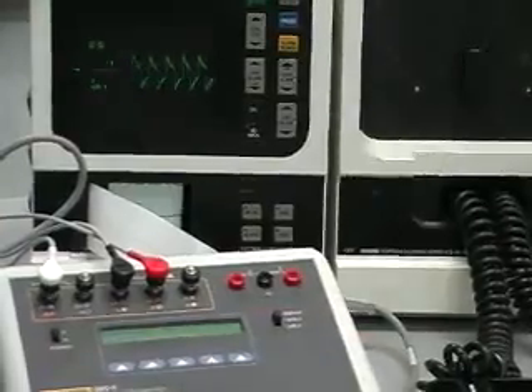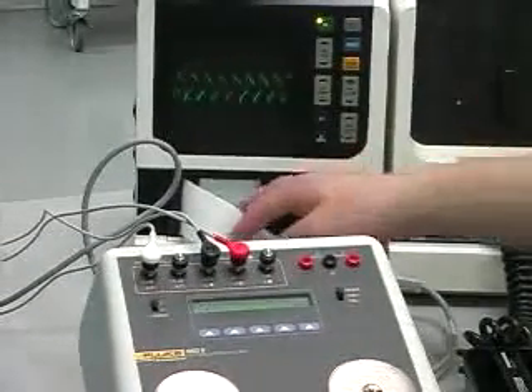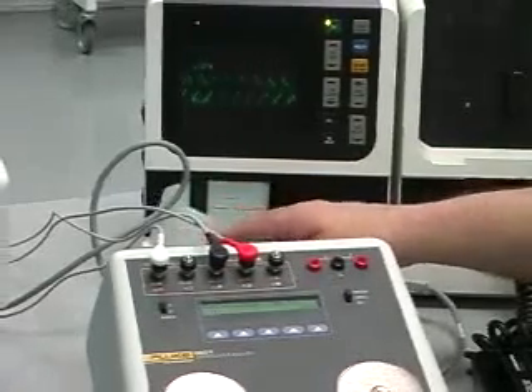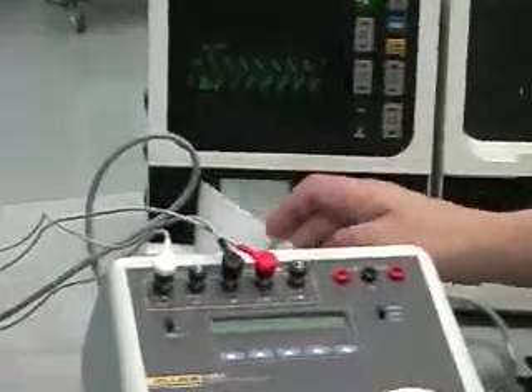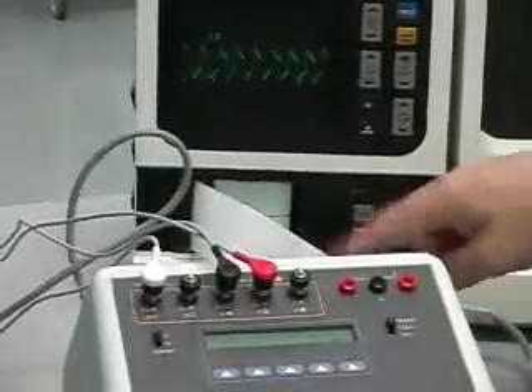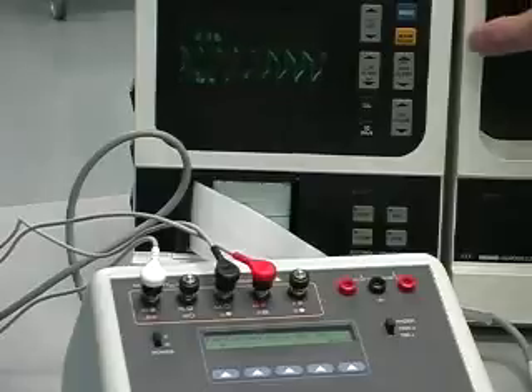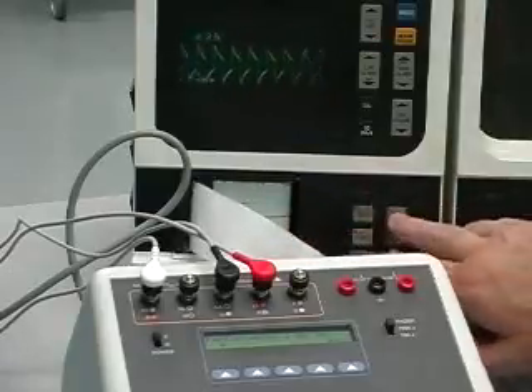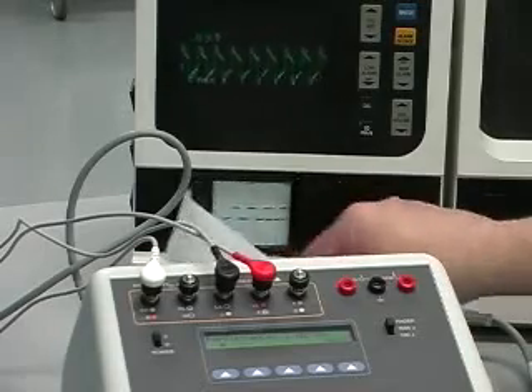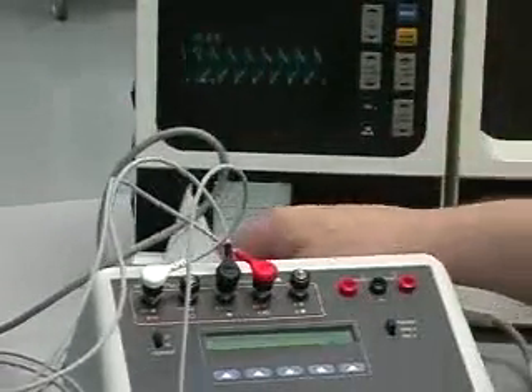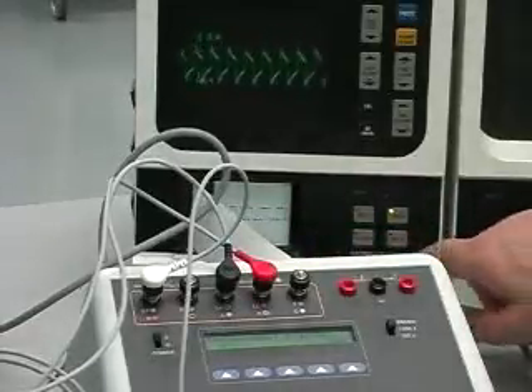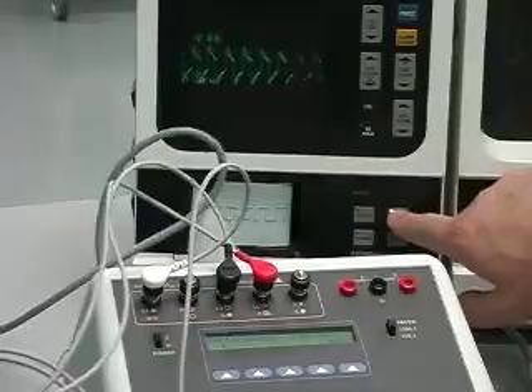Okay, performance waveforms are what you would use for looking at gain and damping. This waveform is good for looking at the low-end frequency response and gain. It operates very similar to the 1 millivolt internal cal test for the unit. So go to diagnostic. Yeah, there it is, a little bit better. So we're looking pretty good. We're looking at a 1 millivolt square wave.